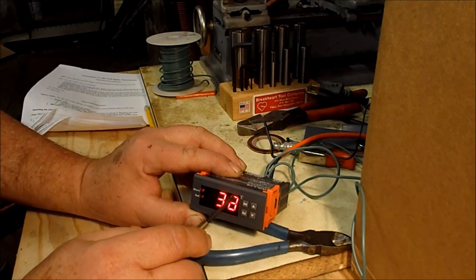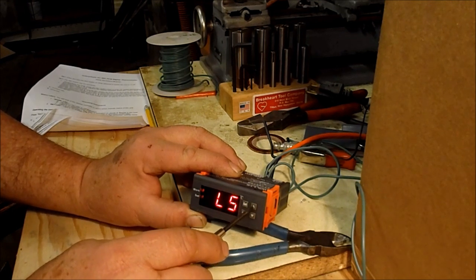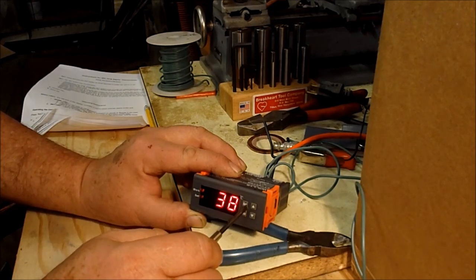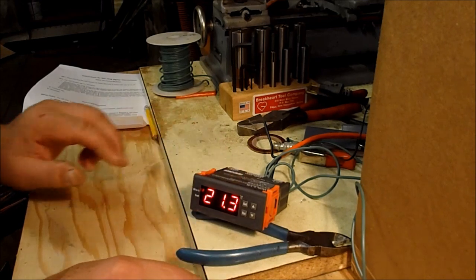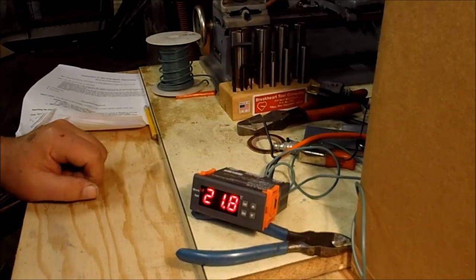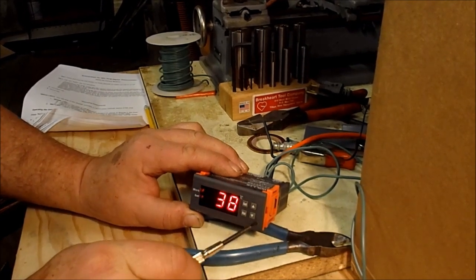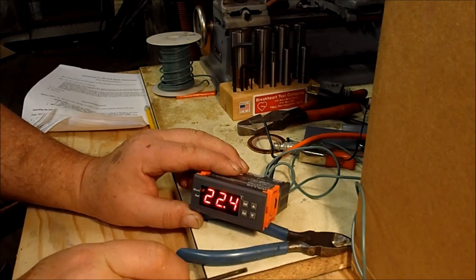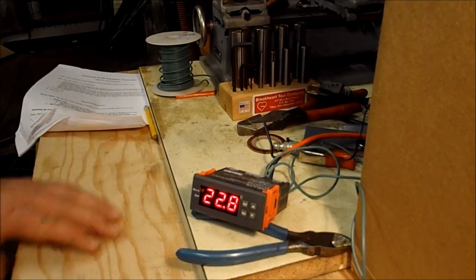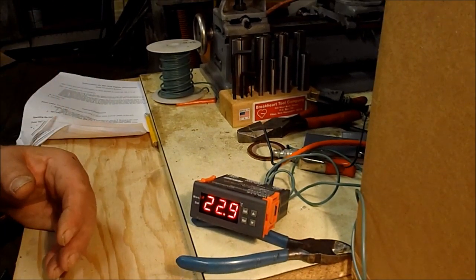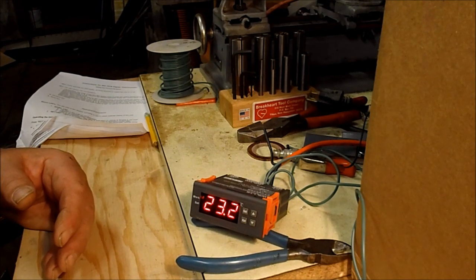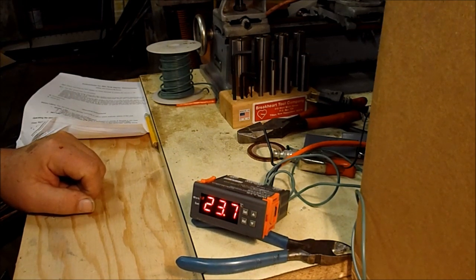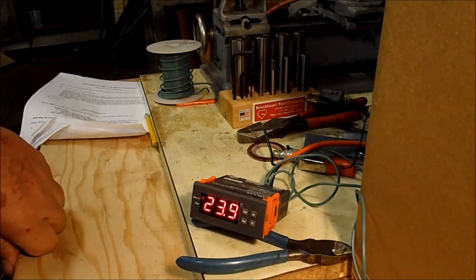Now the high is set for 38 degrees too, so once you get that jumper put in there, that can't be changed. All the parameters are locked in. The thermostat is set to 38 degrees and nothing can let it change. It has a one degree differential on there, so it'll go up to 38 degrees and drop down one degree to 37, and it'll kick the heater back on. That's how she works.